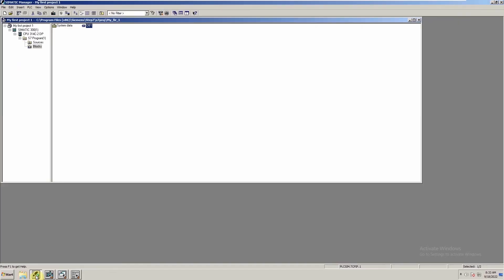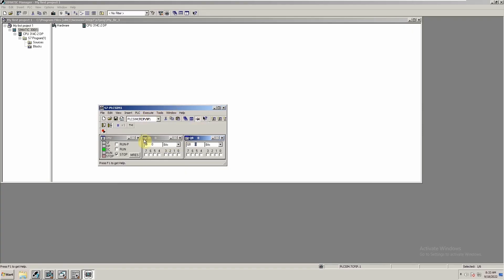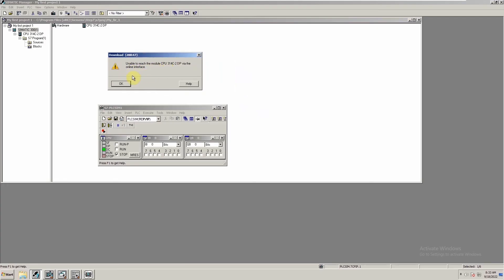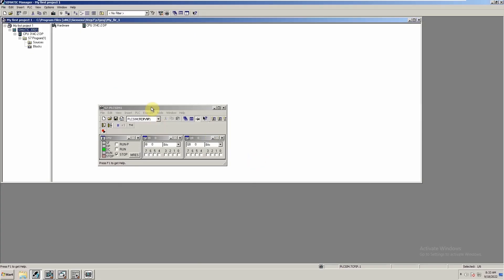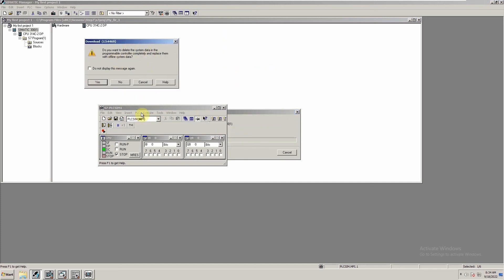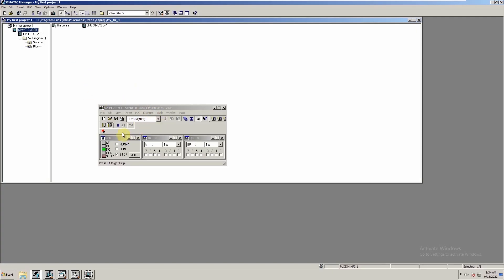To test this ladder logic, we go back to the project, select the S7-300 station, and turn on the simulation. Once the simulator is loaded, we load the program into it. We select the S7-300 station and click the Download button. We select MPI communication, then repeat the same step — select S7-300 and click the Download button. It says all data in the PLC will be replaced — we click Yes to proceed. The program is now downloaded into the CPU.